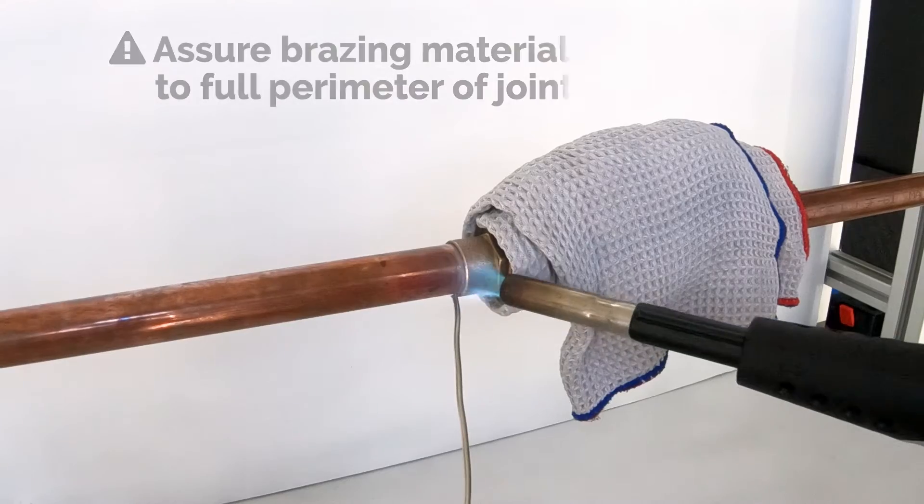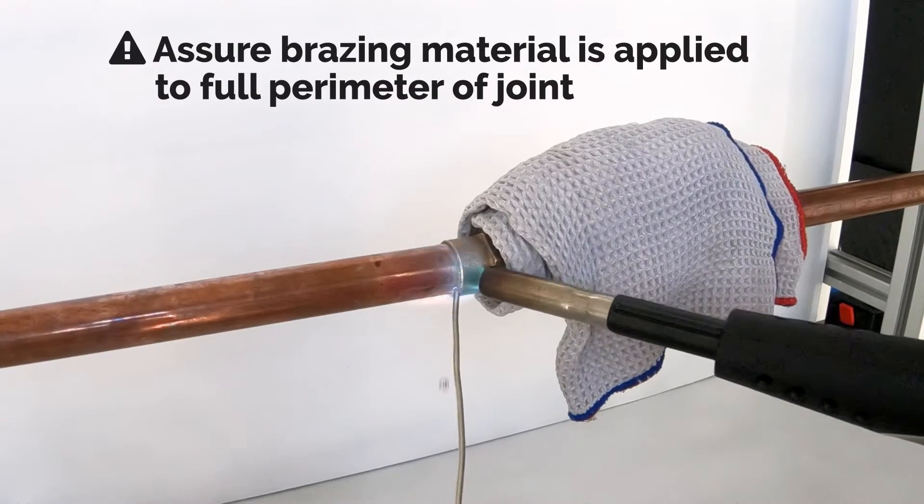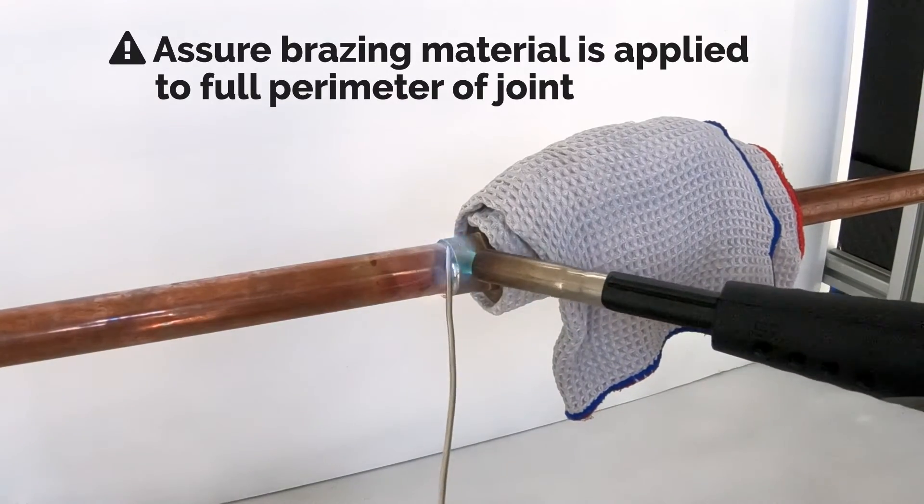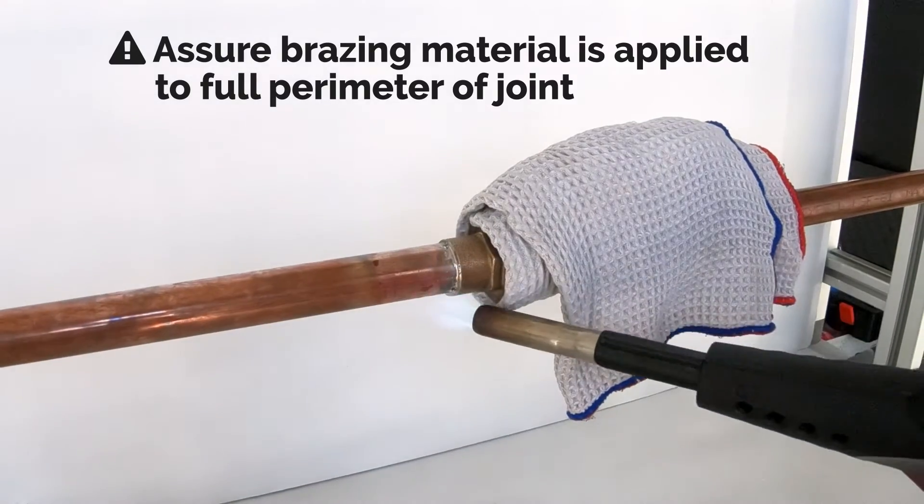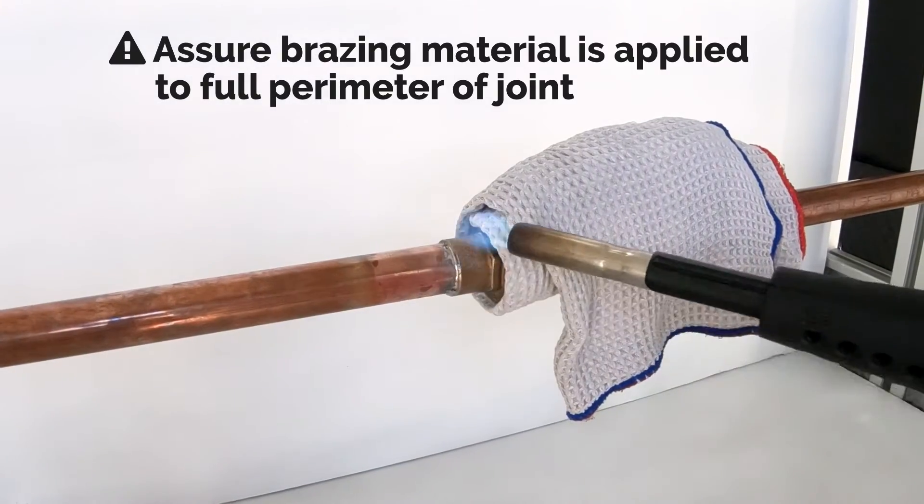Now referring to horizontal installations, start applying the filler metal at the bottom of the joint, then upward. By starting at the lowest position, a dam will be created within the joint to reduce runoff of filler material throughout sweat process.